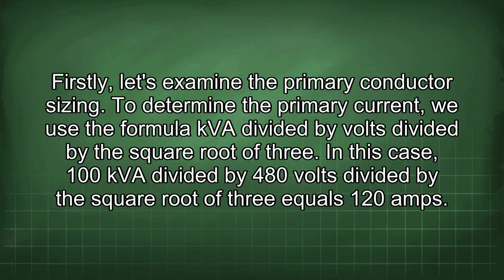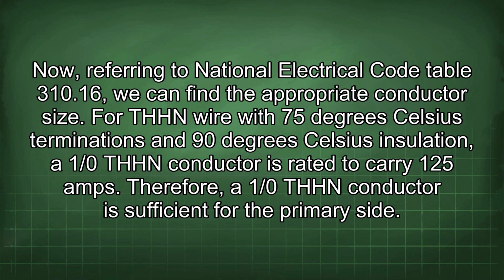To determine the primary current, we use the formula kVA divided by volts divided by the square root of 3. In this case, 100 kVA divided by 480 volts divided by the square root of 3 equals 120 amps. Now, referring to National Electrical Code Table 310.16, we can find the appropriate conductor size. For THHN wire with 75 degrees Celsius terminations and 90 degrees Celsius insulation, a 1/0 THHN conductor is rated to carry 125 amps. Therefore, a 1/0 THHN conductor is sufficient for the primary side.